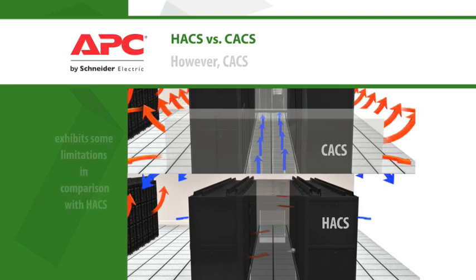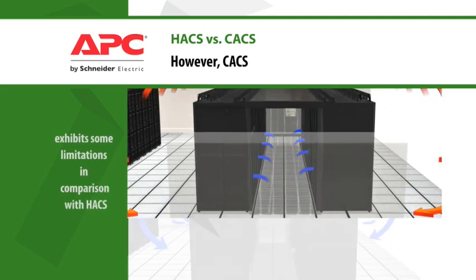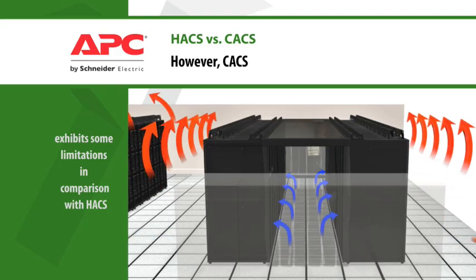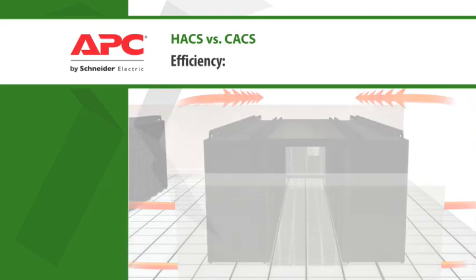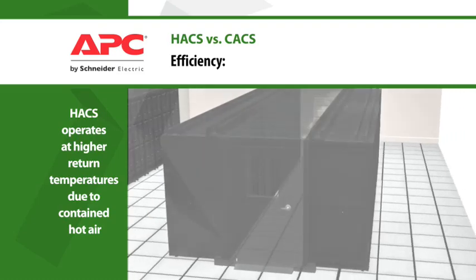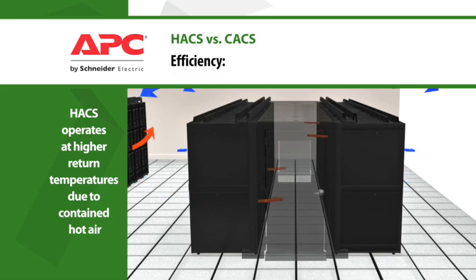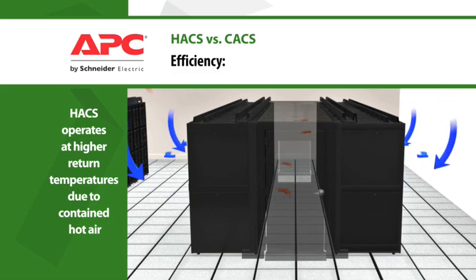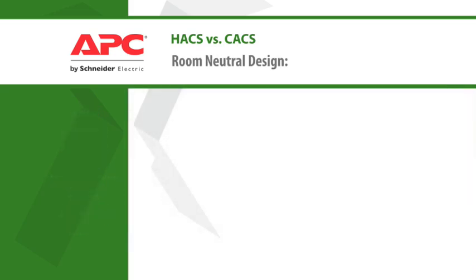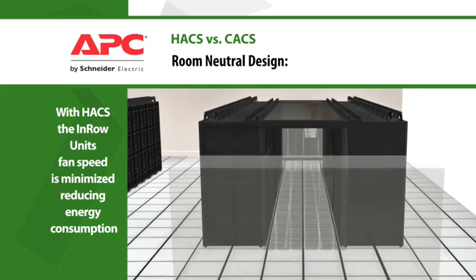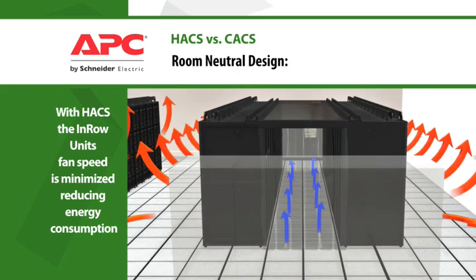While both the hot aisle and cold aisle systems help solve today's data center challenges, the cold aisle containment exhibits some limitations in comparison with the hot aisle system. With the hot air contained, the in-row cooling units are able to capture all of the heat from the IT equipment. Mixing from the room is also eliminated, which increases the return temperature, increasing cooling capacity and efficiency. With mixing eliminated, the in-row cooling system's fan speed is minimized, further reducing energy consumption.